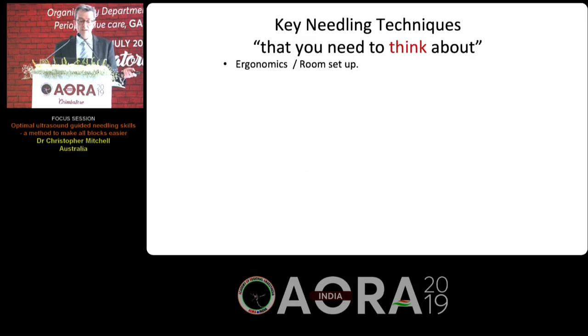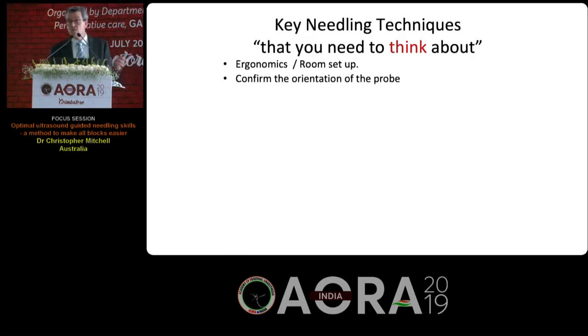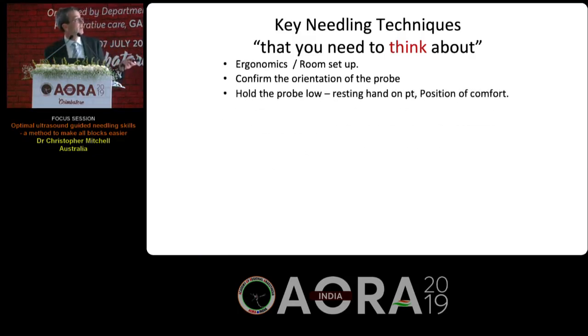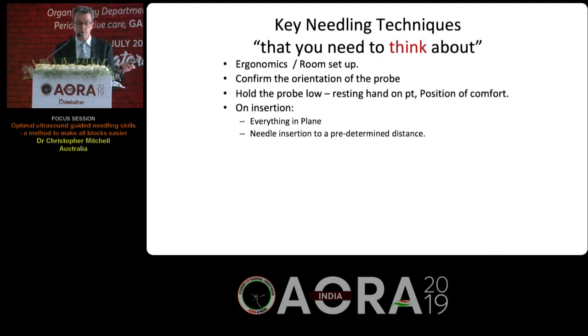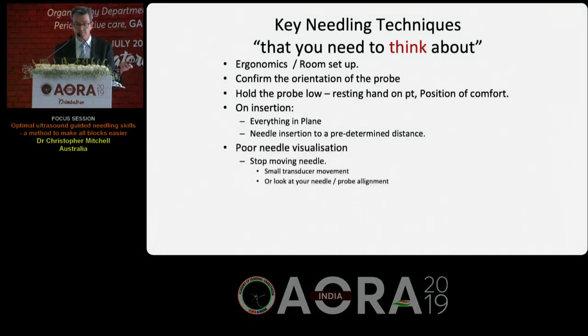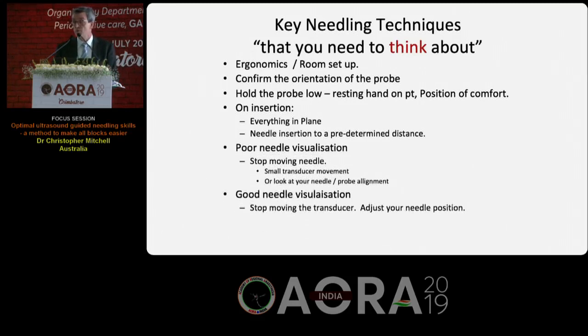So with needling, key things to think about: get your ergonomics in your room set up correctly at the start. Always confirm the orientation of your probe. We haven't gone over that, but make sure you hold the probe low so that you're resting on the patient so it doesn't move. On insertion, make sure that everything's in plane and that you're going to insert your needle a predetermined distance and a predetermined angle. If you've got poor needle visualisation, stop moving your needle and move the probe to find it. And once you have got good needle visualisation, then you just hold your probe nice and still, don't move it at all, and now you're moving your needle.